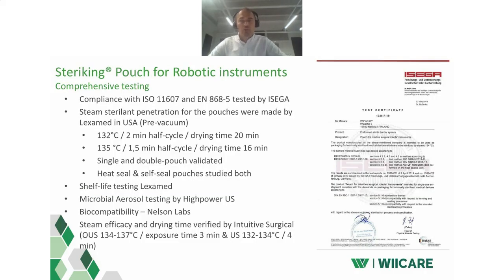But of course, it was not enough to do only the right size of pouch, which is strong enough and has good aseptic opening and so on. Obviously we needed to test that all these properties are according to the needs, so that it provides a sterile barrier. And we tested the product in ISEGA laboratory in Germany to be compliant with ISO 11607 and EN 868 Part 5. And then in the United States, we made steam sterilant penetration testing for the pouches at Lexamed.